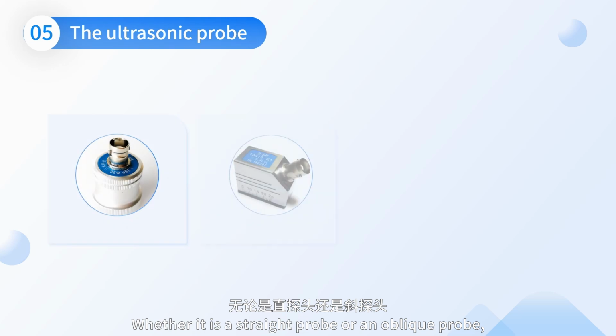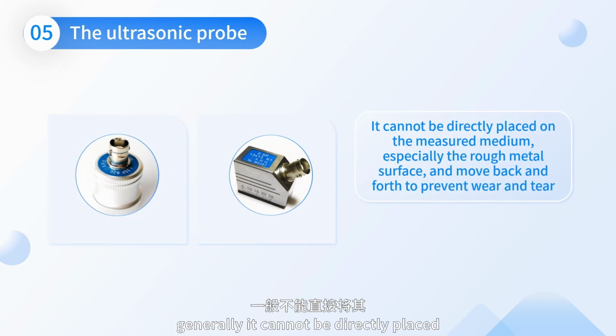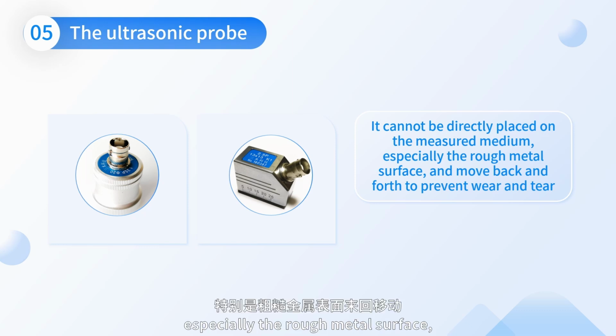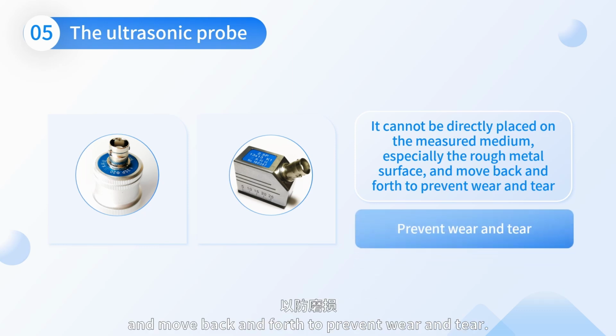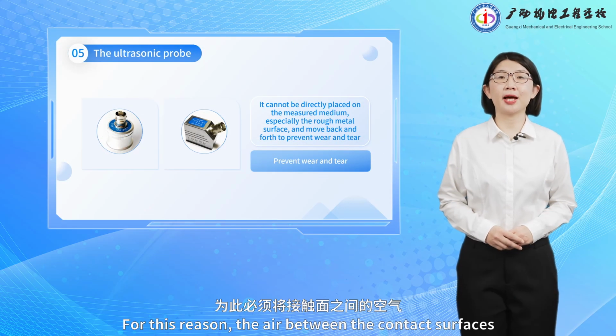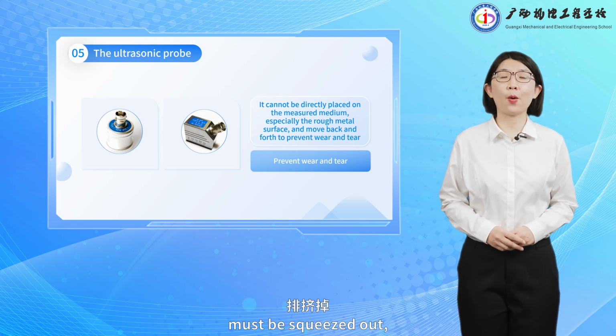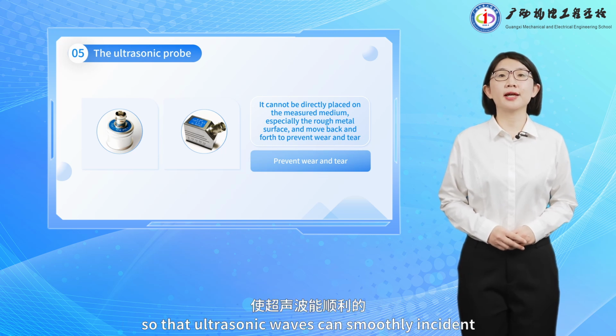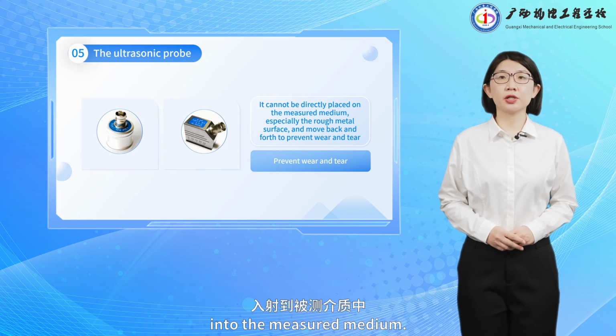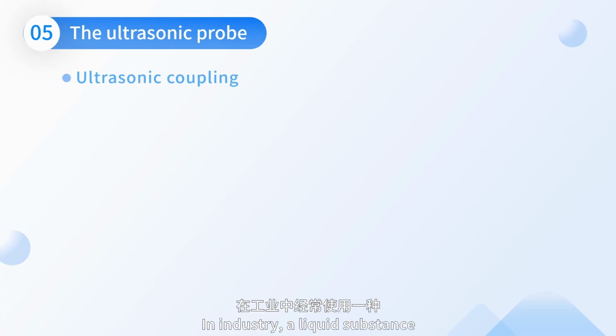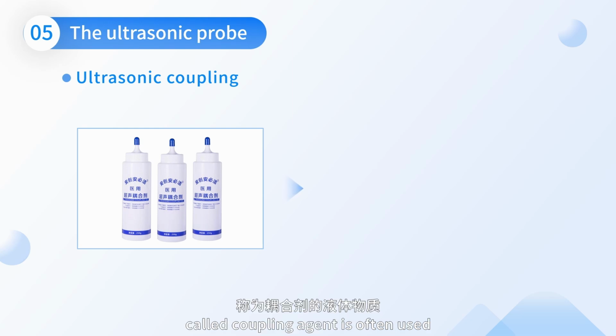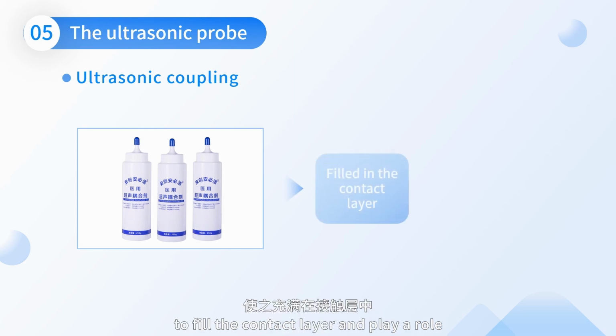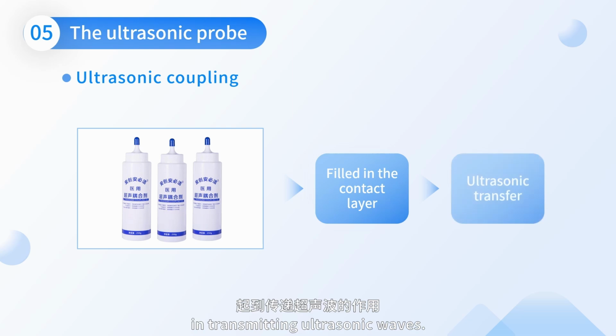Whether it is a straight probe or an oblique probe, generally it cannot be directly placed on the measured medium, especially the rough metal surface, and moved back and forth, to prevent wear and tear. For this reason, the air between the contact surfaces must be squeezed out, so that ultrasonic waves can smoothly be incident into the measured medium. In industry, a liquid substance called coupling agent is often used to fill the contact layer and play a role in transmitting ultrasonic waves.